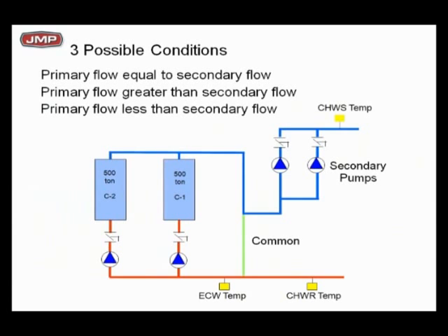There are three possibilities of what's going to happen with these chillers in the primary secondary. Go back to your basics, remember? The primary flow rate could equal the secondary flow, the primary flow rate could be greater than the secondary flow, or the primary flow could be less than the secondary flow. What will happen to these temperatures as we do that? I think it's important you put all this information together that you've learned, and let's see what happens to the temperatures as we play with this. So let's take each one of these cases, put some numbers and temperatures to it, and just see where we are. I think you'll enjoy doing this.